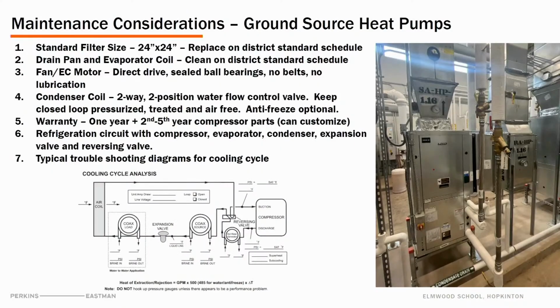There are some controls. Every system has some level of controls to make things turn on and off, and set point control. So there are control valves at each one of these units. This one's actually inside this cabinet, so you don't even see it here. When the unit's off, we shut the water off. When the unit's on, we open the water flow up. This is the ground source heat pump piping here that drops down, goes into the unit, comes out of the unit, and goes back to the well field. So that's what you're seeing there.